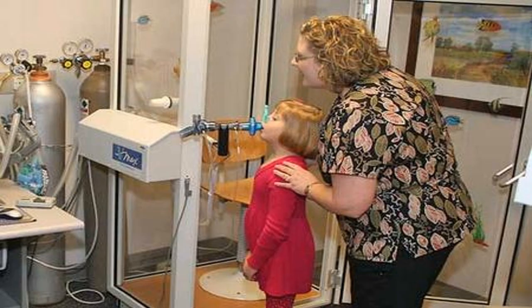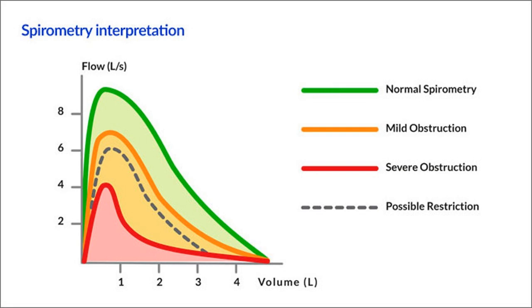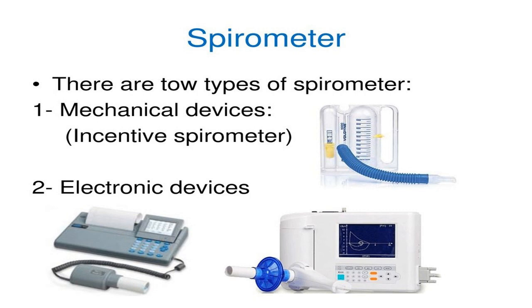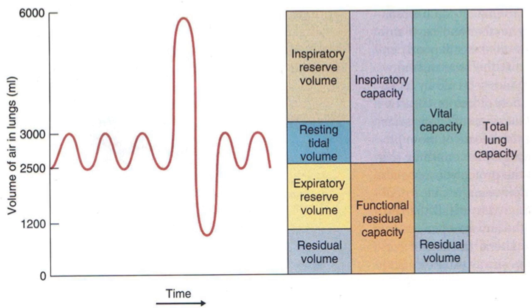Spirometry is also helpful as part of a system of health surveillance in which breathing patterns are measured over time. Spirometry generates pneumotachographs, which are charts that plot the volume and flow of air coming in and out of the lungs from one inhalation and one exhalation. The spirometry test is performed using a device called a spirometer. Most spirometers record and display a graph called a spirogram — a volume-time curve showing volume in liters on the y-axis and time in seconds on the x-axis — as well as a flow-volume loop depicting the rate of airflow on the y-axis and total volume of inspired or expired air on the x-axis.